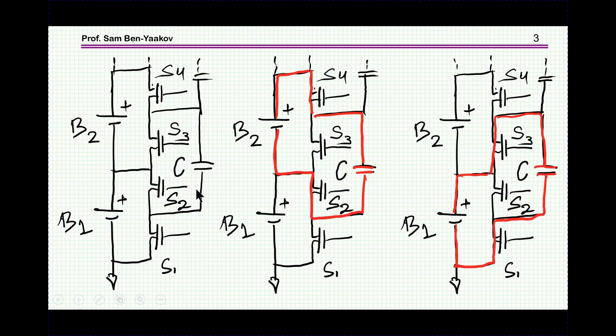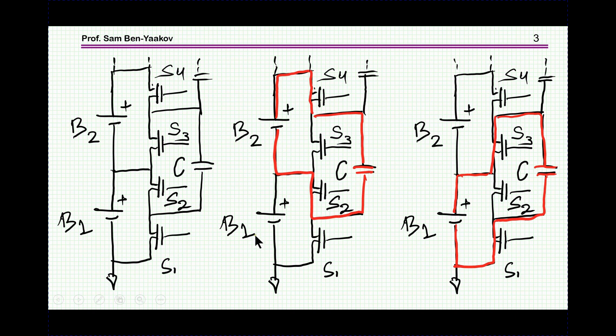Here we can see it in a little more detail. Say we have two batteries, we have two switches per battery, we have the capacitor, and then when the upper switches are on, this capacitor is connected to this battery. When the lower switches are on, the capacitor is connected to the lower battery. So if one battery has a higher voltage than the other, the capacitor will be charged to a higher voltage and then deliver charge to the battery with the lower voltage. Eventually, this process will propagate throughout the string and all the batteries will be balanced.